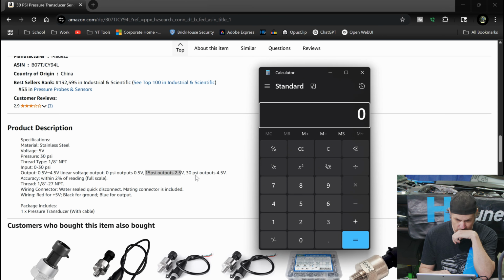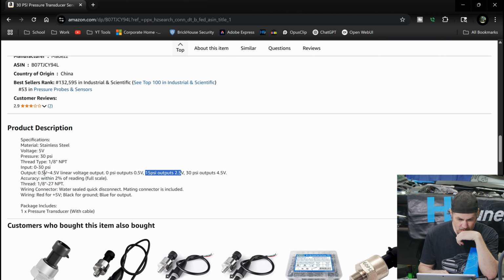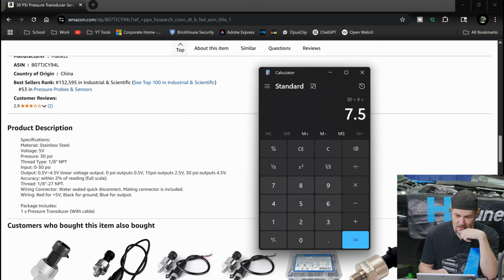Let's open up the calculator. We're at 0.5, so 4 volts is our sweep range. Clear this - 30 PSI divided by 4 means each volt is 7.5, so our slope should be around 7.5. Then our offset should be half of that, times 0.2 or 0.5. Come on now - 375 should be our offset.